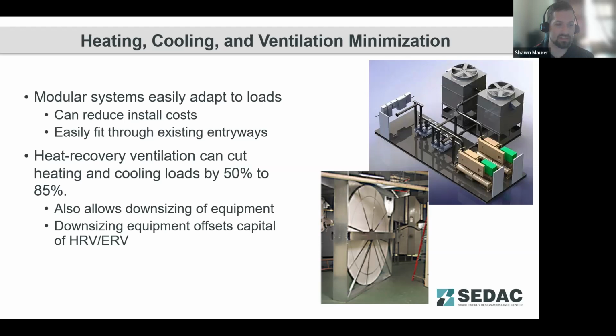Heat recovery ventilation, depending on whether you're doing heat only or total energy recovery, can reduce heating and cooling loads by 50 to 85%. And again, if you're reducing those ventilation loads, you can also reduce the capacity of the equipment and save on the capital cost of that heating and cooling capacity. So you can put in smaller chillers and boilers to begin with, or smaller heat pump systems.